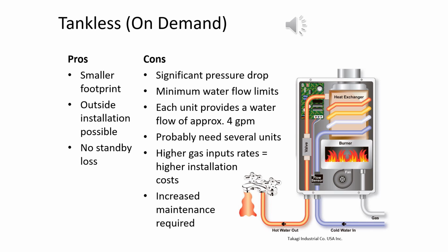Tankless water heaters have become much more popular in smaller commercial food service facilities over the course of the last 10 to 15 years. They're sought after because of their smaller footprint and because outside installations are possible, which frees up space in the facility. These units also boast that they don't have a standby loss because they don't store hot water.